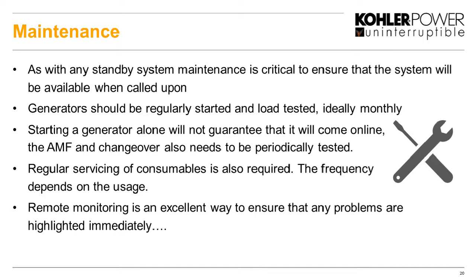Actually starting the generator on its own will not guarantee it will come online. One of the big problems we see is people start generators but don't actually bring it online. So they don't test the AMF panel, they don't test the changeover. This also needs to be tested periodically to make sure that when you need it, it will happen. Okay, so it's a critical thing to do.